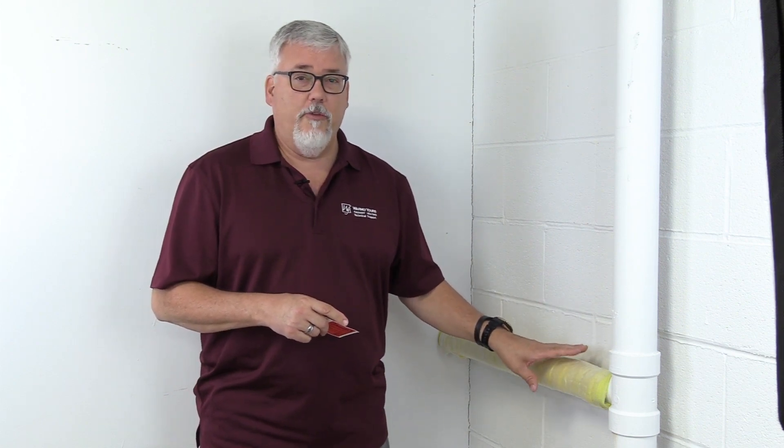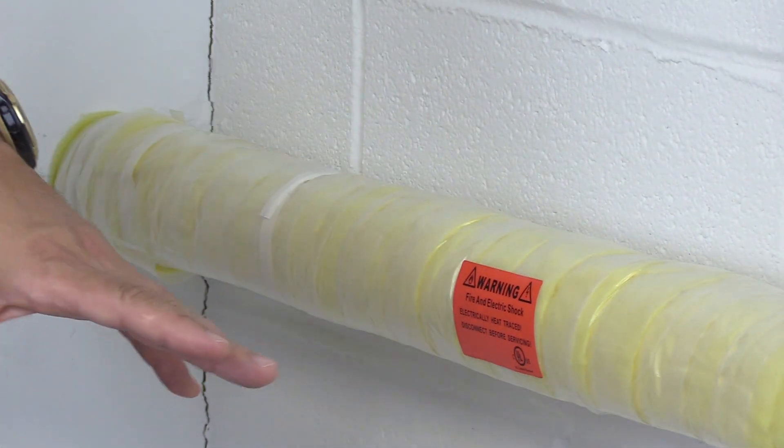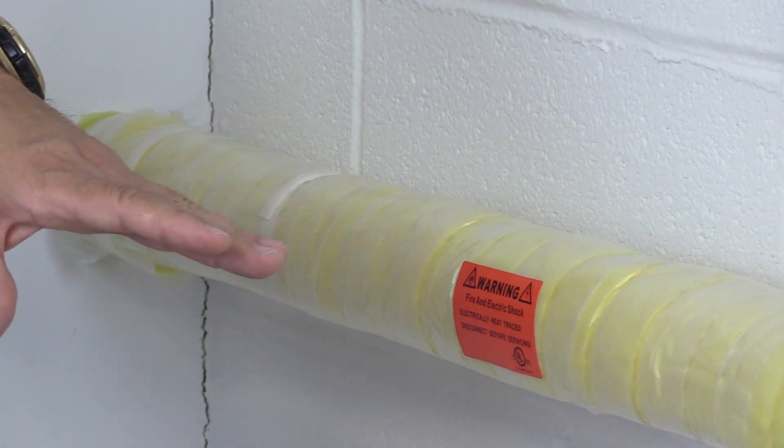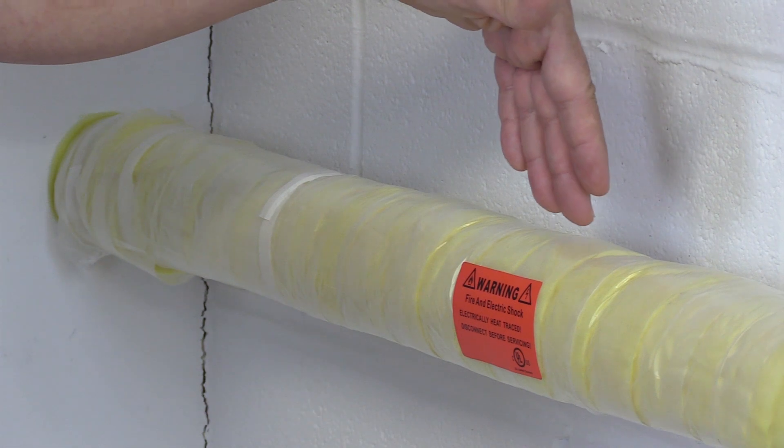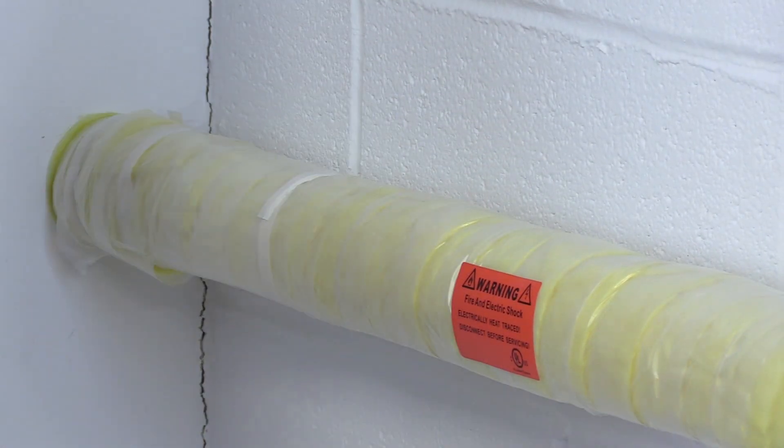Okay, now that we have installed the insulation and the waterproofing over the pipe, it's time to install the warning labels. Warning labels should be placed every 10 feet on the pipe. When you place the label on the pipe, you want to make sure that it's visible from where people will be working on it. So you don't want to put it on the top where no one will ever see it. You want to put it in a visible location where people will be able to see it.